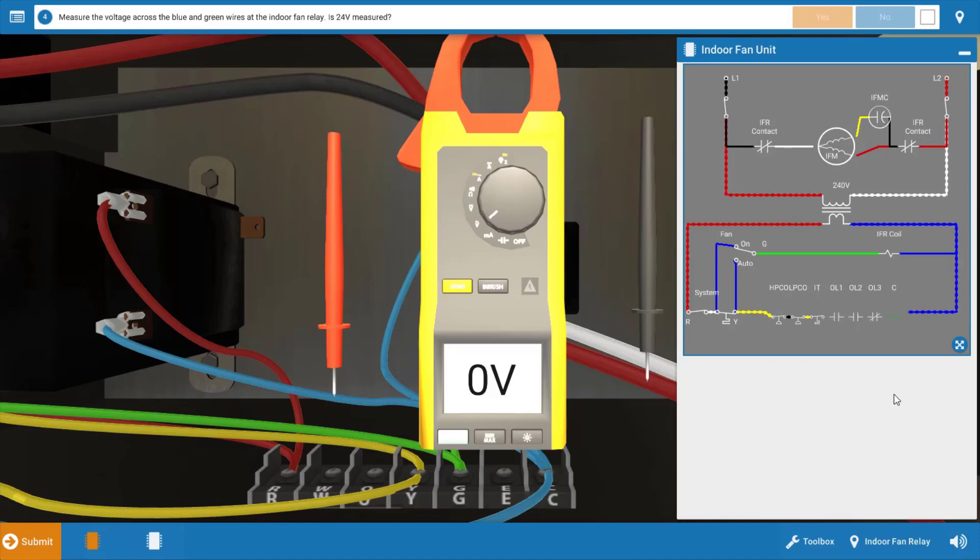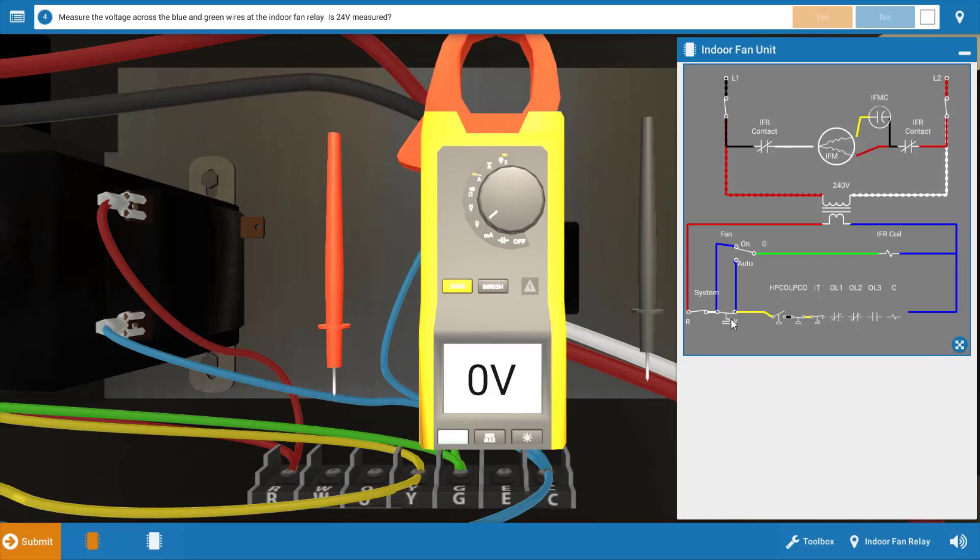So our possibilities here are either the motor, the capacitor, the relay, or possibly the thermostat, just the fan switch in the thermostat. We know that the cooling contacts are closing because the contactor is energized and turning the outdoor unit on.